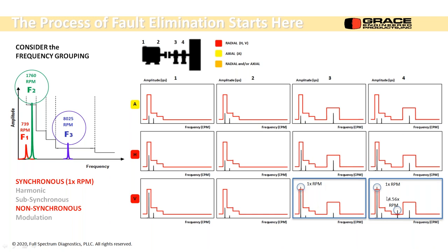I also have at position 4 in the vertical direction, that same 1 times RPM problem, but I have a 4.56 times running speed. I have a non-synchronous frequency in there. Okay, so my two different frequencies of interest are 1760 and 8025. One is synchronous, one is non-synchronous. So I'm going to split those two up. I'm going to first do the analysis on the synchronous frequency and then do the other.